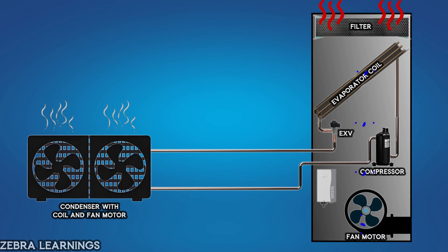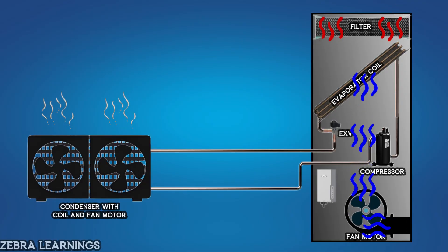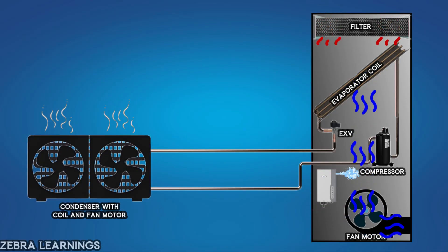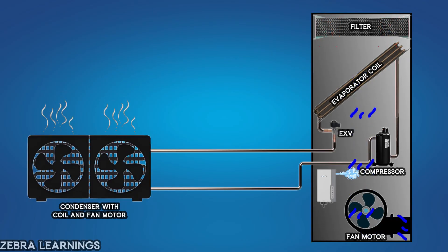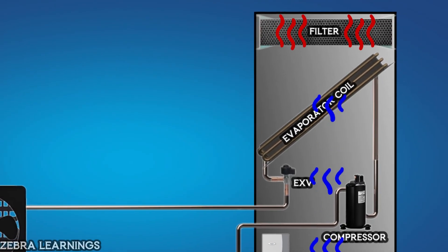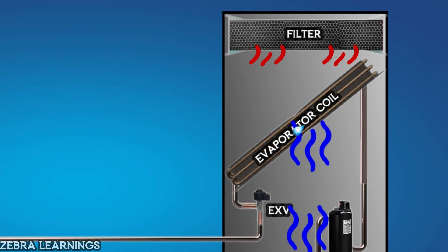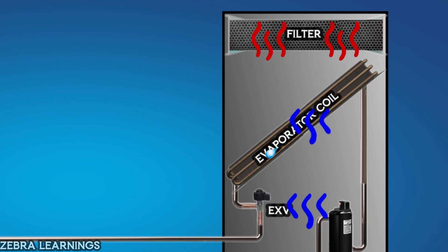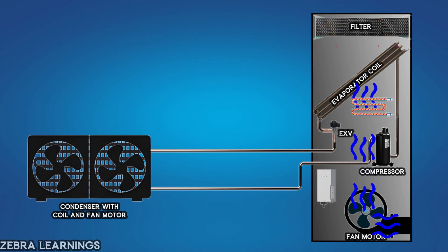To maintain the desired humidity level in a data center, PACs employ various mechanisms to adjust the moisture content of the air. When the humidity level drops below the desired range, the humidifier generates water vapor, which is then mixed with the air stream and distributed through the supply duct, increasing the humidity level and bringing it back to the target range. Conversely, when the humidity level exceeds the desired range, the evaporator coil — responsible for cooling the air — also plays a role in dehumidification. As the air passes over the cold coil, its temperature drops, causing water vapor to condense and form water droplets, which are then removed from the air stream, effectively reducing the humidity level. In some PAC units, additional components like heaters or dehumidifiers may be employed to further refine humidity control.